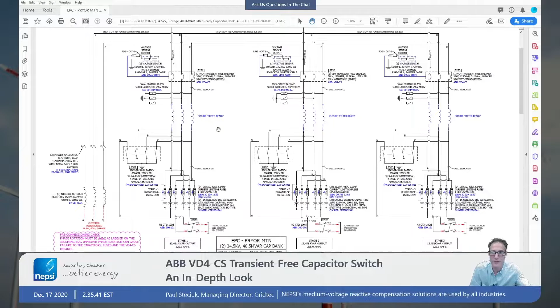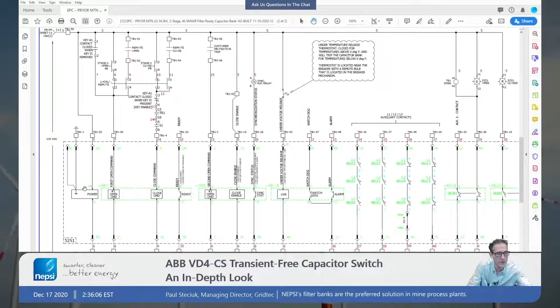And this is a pretty typical control diagram for a circuit breaker. It has a lot of the same elements a standard circuit breaker has, but it has other things like watchdog type information in the CPU, and perhaps maybe we can get ABB to share some of that stuff with us. But here we show that there's a power supply coming in here. There are 2 open inputs. We can open this breaker through 2 different inputs, input 1 here and input number 2 there. So we typically use 1 for protection and 1 for control. So in this case, we're using open number 1 for control.